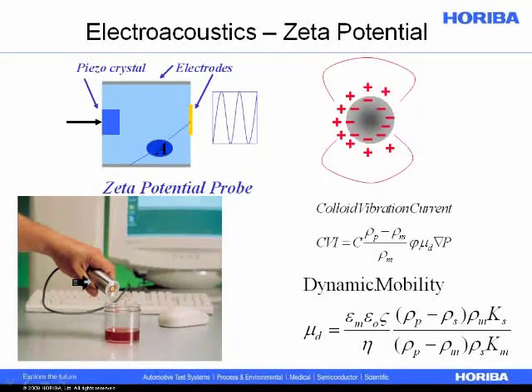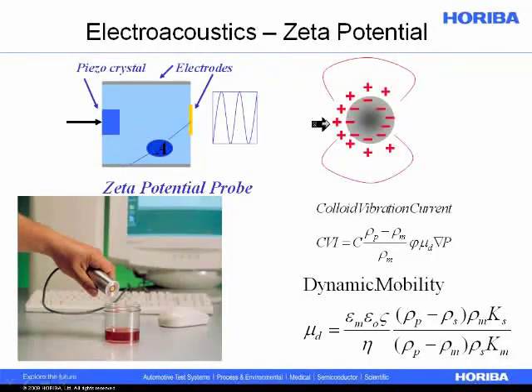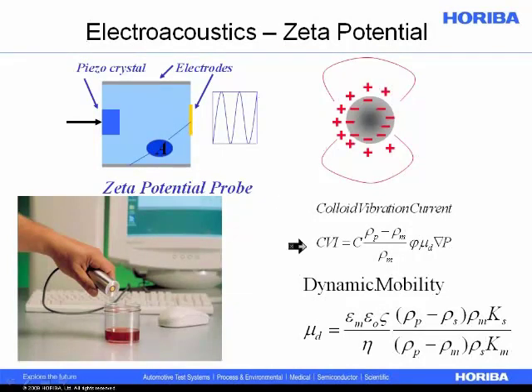What we do is oscillate an acoustic wave through a sample going out through a gold coating. The particles directly in front of this part of the rod are exposed to an oscillating acoustic wave. Since the particles have more inertia than the liquid and it's an oscillating wave, we build up a dipole moment of ions on the surface of the particle — a disproportionate charge on the left and right. We build up a dipole moment, creating a small current through these particles. We calculate that vibration current and from there can measure the zeta potential.